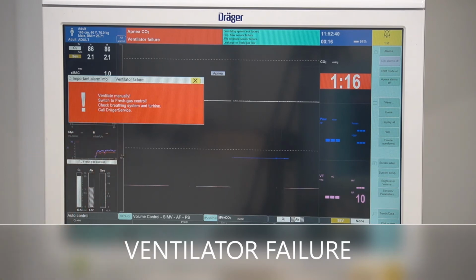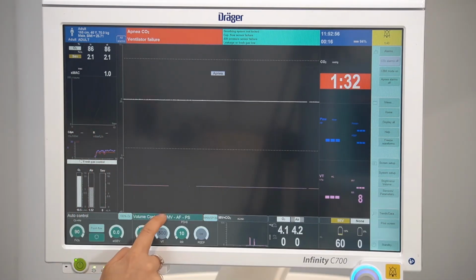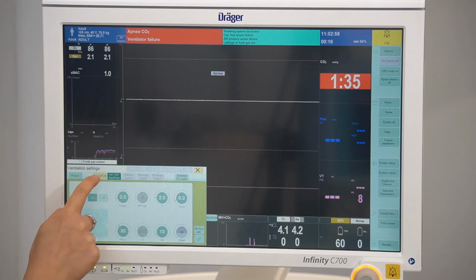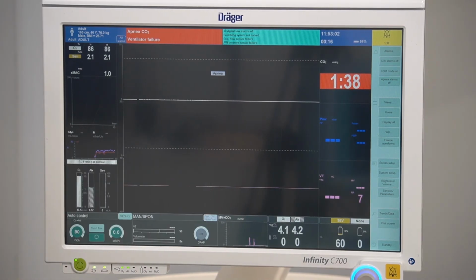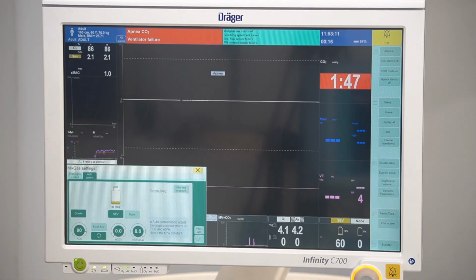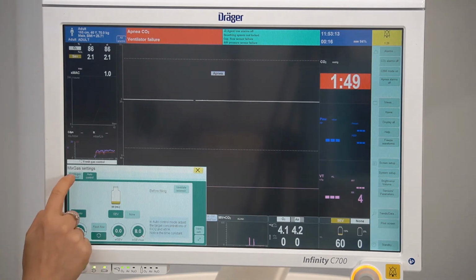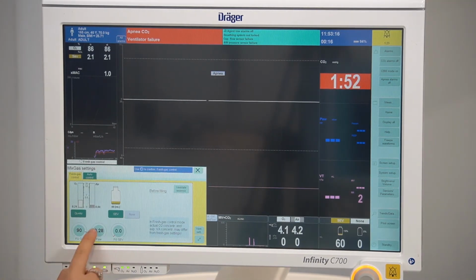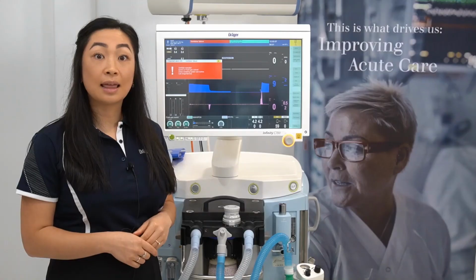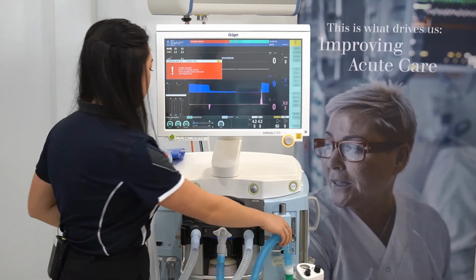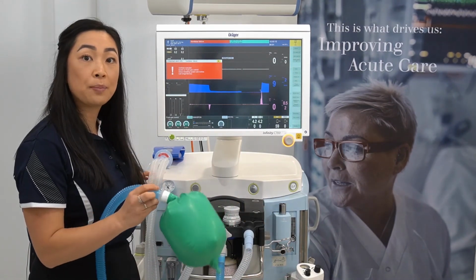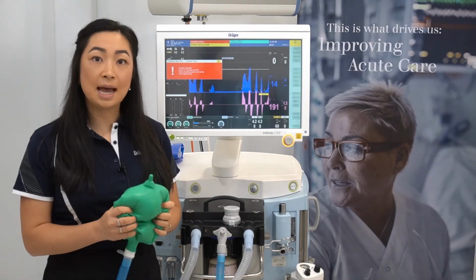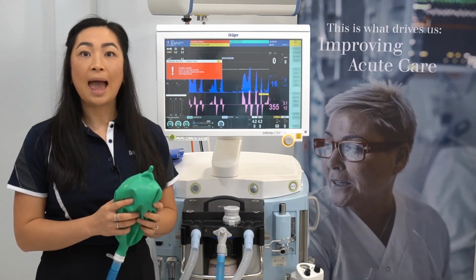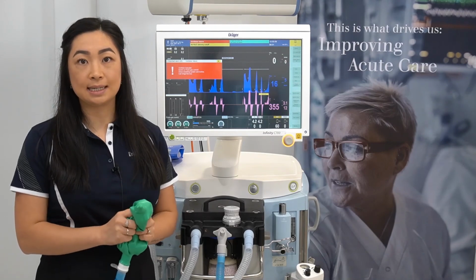In the event of a ventilator failure, the user will need to switch over to manual spontaneous mode. You will see that CPAP will be unavailable. You will also need to switch to fresh gas control mode. Verify your settings. Then verify your APL valve. Use the oxygen flush to rapidly fill the bag if necessary. Then start manual ventilation and contact your technical service representative.